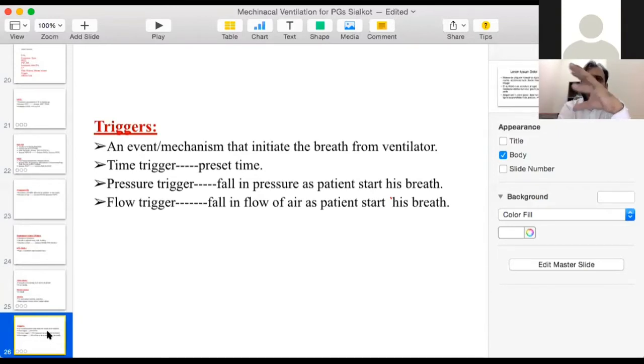The machine, before delivery, will assess whether the patient is in the inspiration phase or the expiration phase. If the patient is in the inspiration phase, only then will the ventilator deliver a breath. If the patient is in the expiration phase, the ventilator will wait, will not deliver a breath, and will wait for some time, and when the inspiration starts, then it gives the breath. So how will the ventilator come to know that the patient is now in the inspiratory phase? This is through triggers. The ventilator gets a message from the patient circuit. How? If the patient starts a breath, you take air. If a slight amount of air moves through the endotracheal tube, there is a sensor near the endotracheal tube, that is the flow sensor and trigger sensor, that will pick up the signal that the patient has taken some air in. So that is called flow trigger.